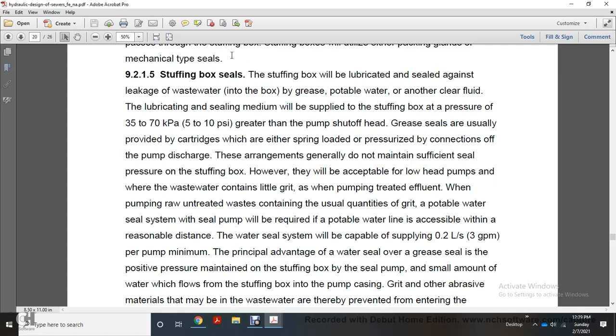These arrangements generally do not seal sufficiently against the pressure of the stuffing box, however they are acceptable for low-head pumps and where wastewater contains little grit, such as when pumping treated effluent. When pumping raw untreated waste in usual quantities, grit is present and a potable water seal system is needed. A seal pump will be required if a potable water line is not accessible within a reasonable distance. Water seal systems will be capable of 3 gallons per minute per pump minimum.